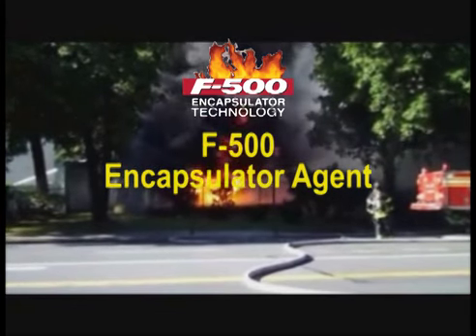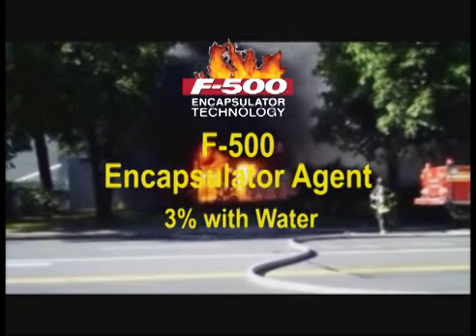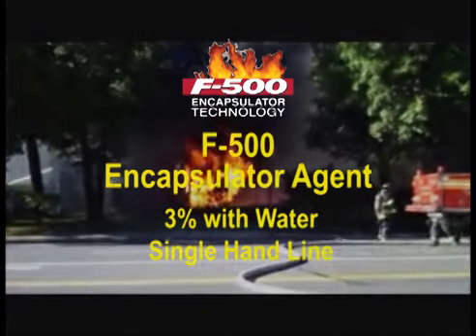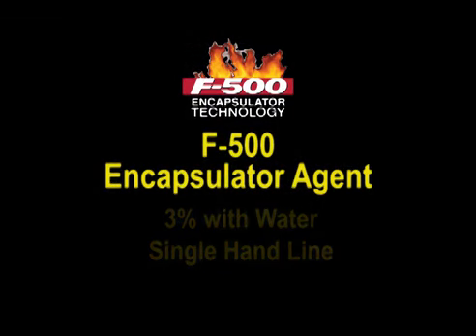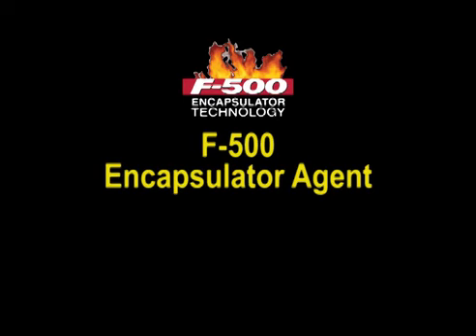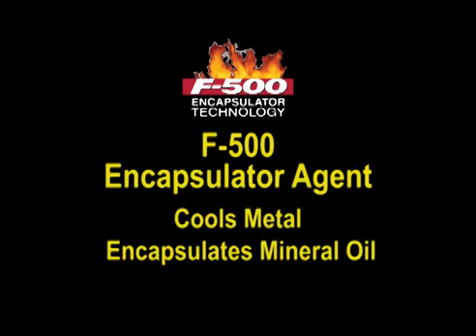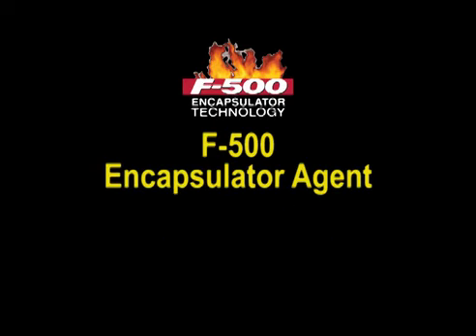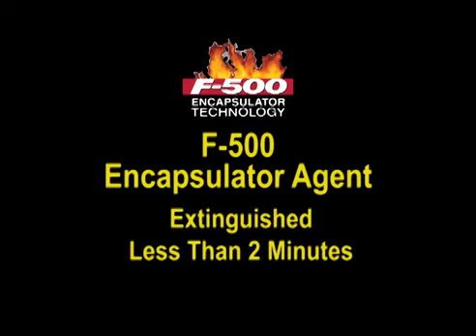The F500 EA was applied at 3% with water through a single hand line. Since F500 EA has the ability to cool the massive metal transformer and encapsulate the oil, F500 EA extinguished the fire in less than 2 minutes. To be safe, they continued to apply F500 EA until the transformer temperature dropped to 120 degrees.